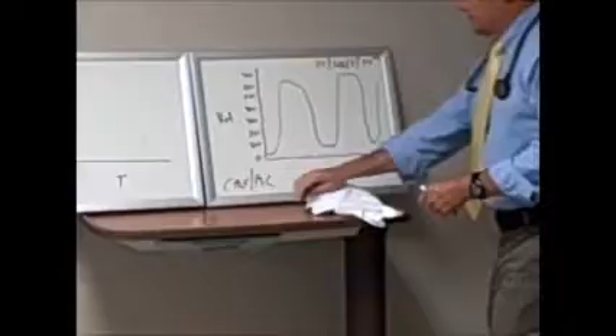The flow set, the tidal volume set. The only thing the patient has any control over if he's awake is when he wants another breath, the machine will give it. Because it's controlled mandatory ventilation or assist control, if he takes this breath after 4 seconds, when will his next breath be? Provided he doesn't want another breath. 6 seconds after that. It's not 6 seconds after this one, it's 6 seconds after that one. The machine presets itself after that. It's a safety mechanism. So let's make this quicker. My scale's too small. 6 seconds apart. Say he wants one at 4 seconds, it'll look the same. The next one after that won't be for 6 more seconds.